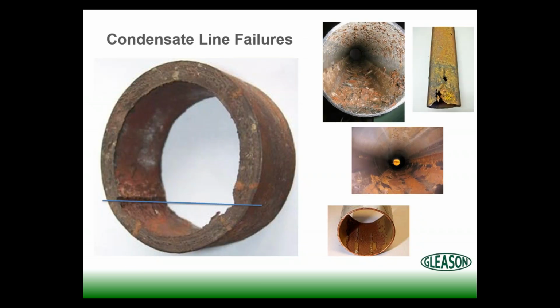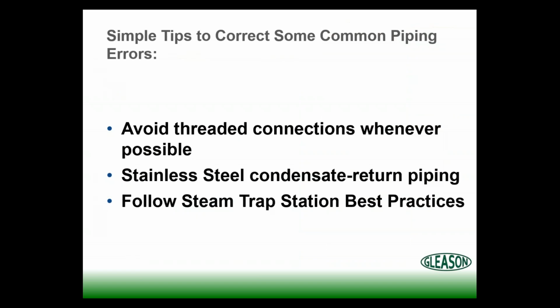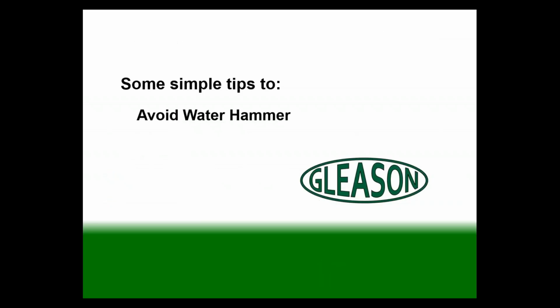So I mentioned the carbonic acid corrosion in some of our condensate lines. Steam best practice calls for using stainless steel as the material there to avoid the carbonic acid corrosion. So again, some simple tips to correct some of those common piping errors. We want to avoid thread connections, use stainless steel condensate return piping if we can, and of course follow our steam trap station best practices.